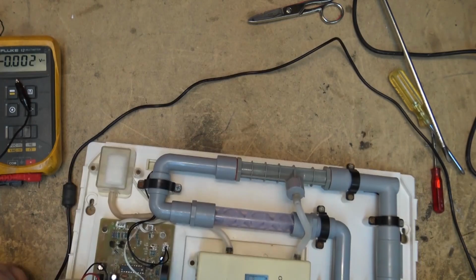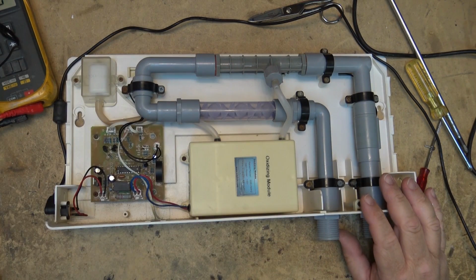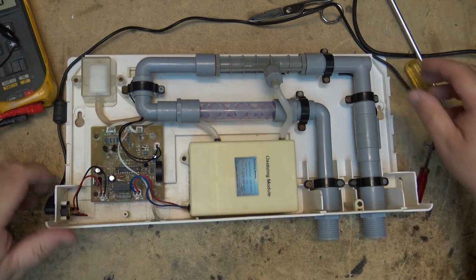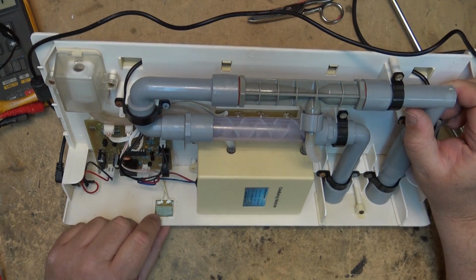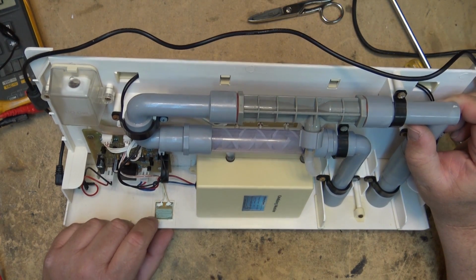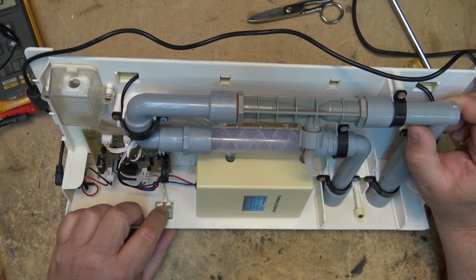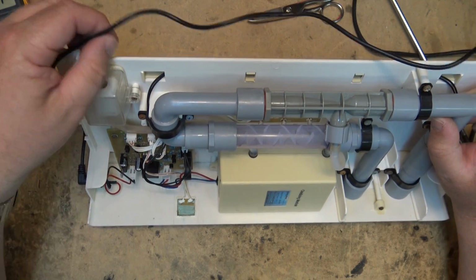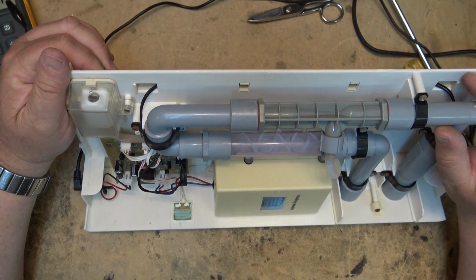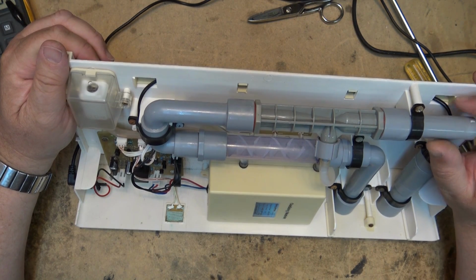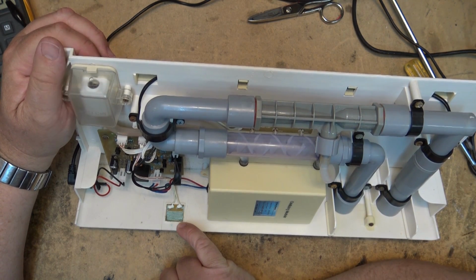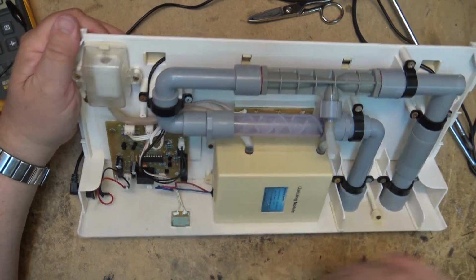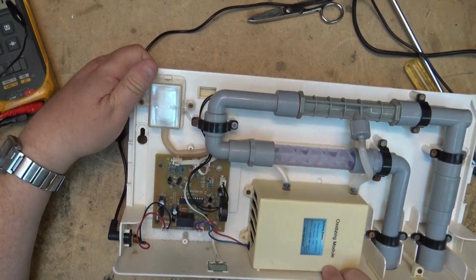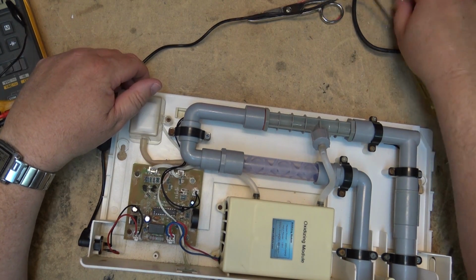So I don't know what to say. I'm thinking maybe what happened on this thing is maybe it had a water leak. This is a water leak detector. Maybe some moisture got in here and triggered it into a shutdown state, and maybe there's a leak, and water leaked into here and shut the thing down, because it certainly appears to be working now when I trigger it.